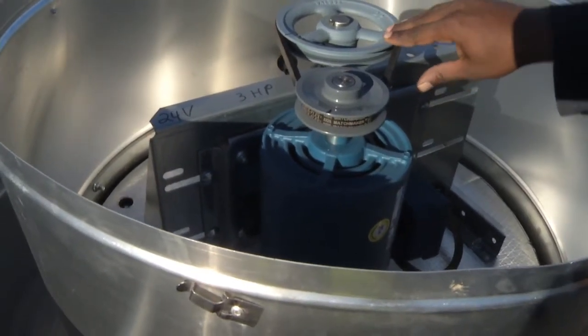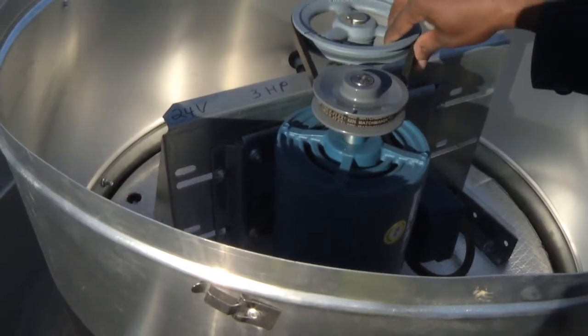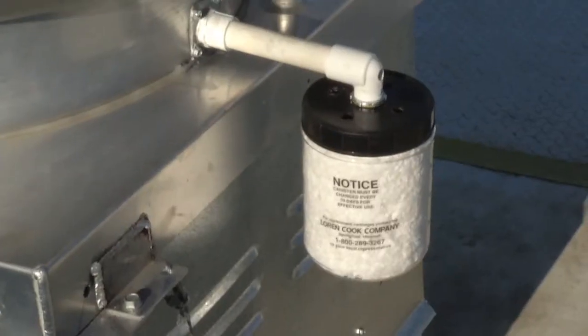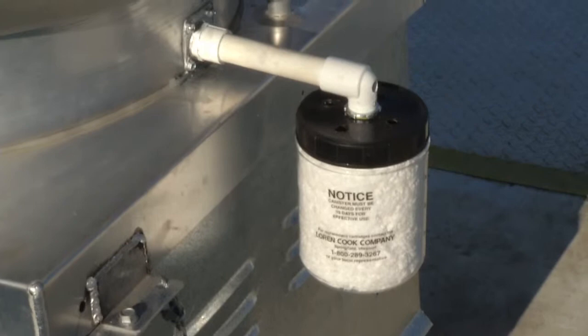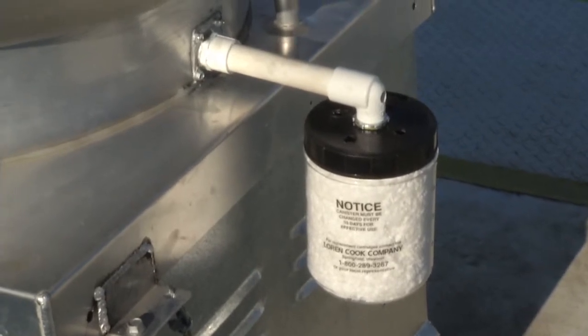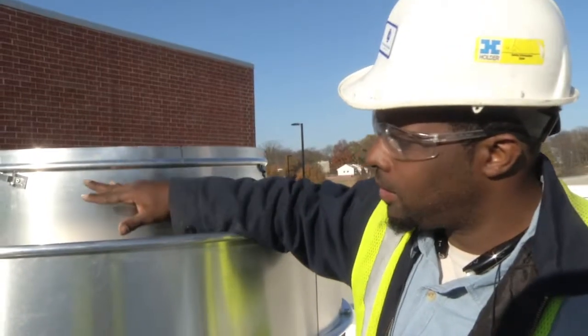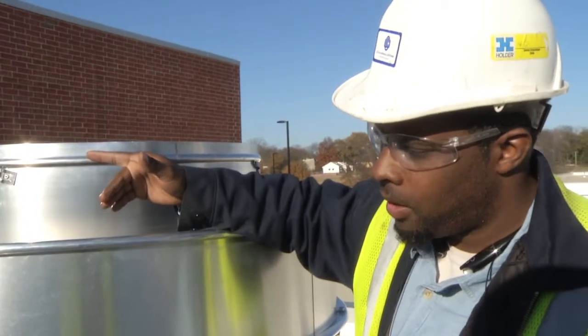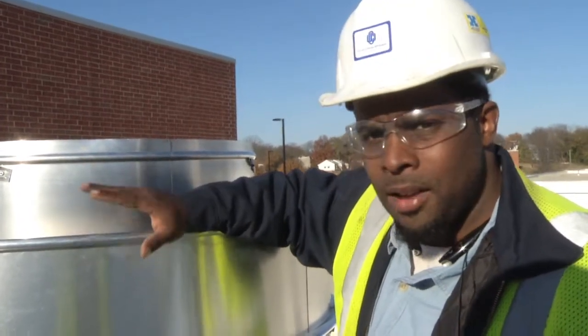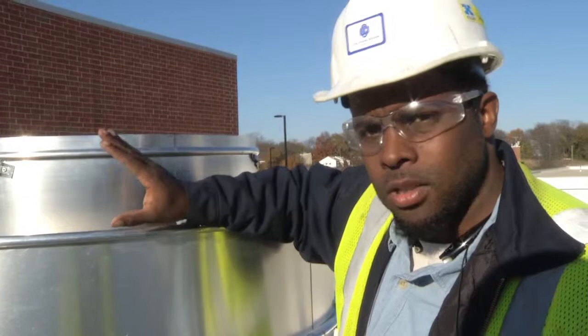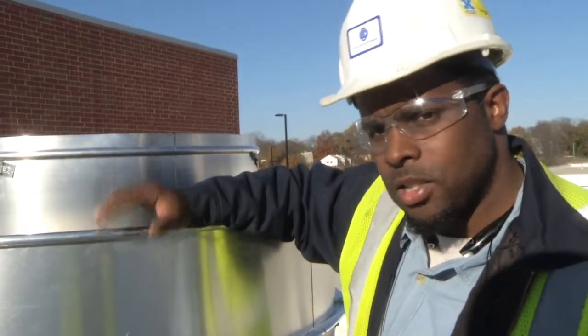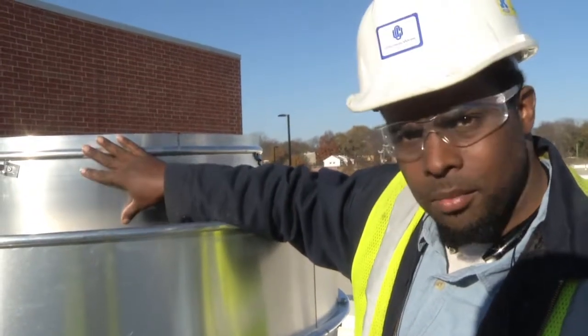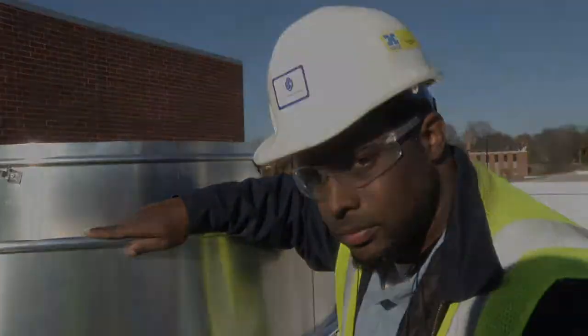You want to check your belt tensioning probably every quarter. You also have a grease interceptor here on the side, which should be checked monthly. This, as the supply air fan, has a frequency drive that's in the exhaust hood down in the kitchen area that should be turned off before killing main power to the unit.